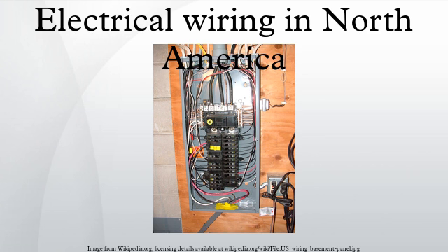Ground fault circuit interrupter protection is required on receptacles in wet locations. This includes all small appliance circuits in a kitchen, receptacles in a crawl space, basements, bathrooms, and a receptacle for the laundry room, as well as outdoor circuits within easy reach of the ground. However, they are not required for refrigerators because unattended disconnection could cause spoilage of food, nor for garbage disposals. Instead, for refrigerators and other semi-permanent appliances in basements and wet areas, a one-outlet non-GFCI dedicated receptacle is generally used.